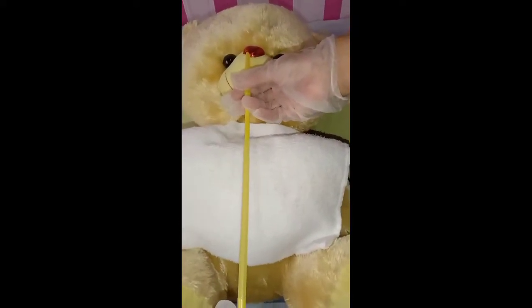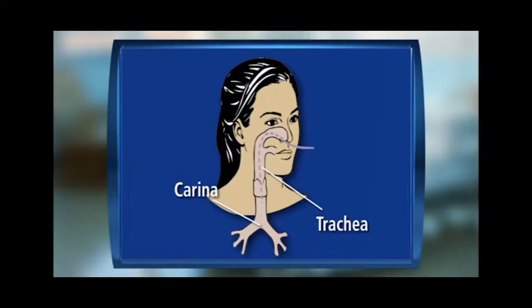As you insert the catheter, do not cover the catheter vent. Follow the natural course of the nares. Orient the catheter downwards, don't force it. If you feel resistance, you've probably hit the carina. In that case, withdraw the catheter 1 to 2 centimeters, between 0.4 and 0.8 inches, before applying suction.